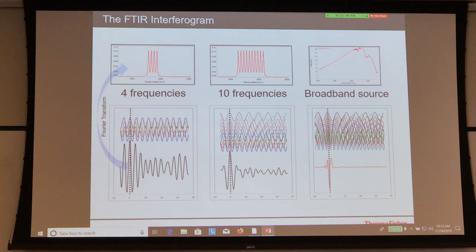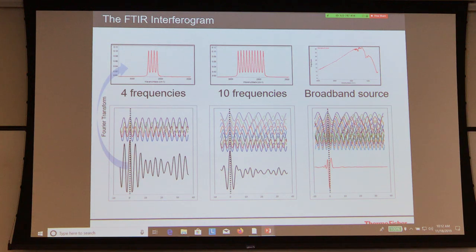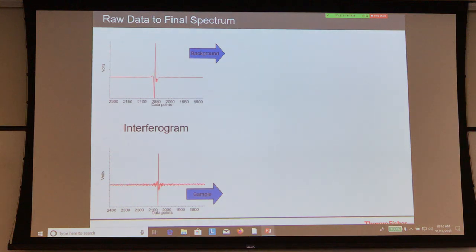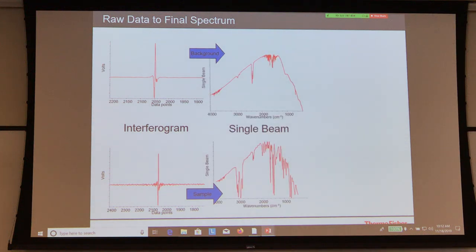Think about four frequencies — it can be as simple as that. Ten frequencies can look more complicated, but what we work with in mid-infrared is an entire region from about 400 to 4,000 wavenumbers. This is a very broad region from a broad source. You end up seeing a really nice center burst with the rest as a flat region — that is your interferogram. The instrument collects the interferogram; all the magic after that is done by the computer. The instrument will collect a background, collect a sample, and from there the software takes over.